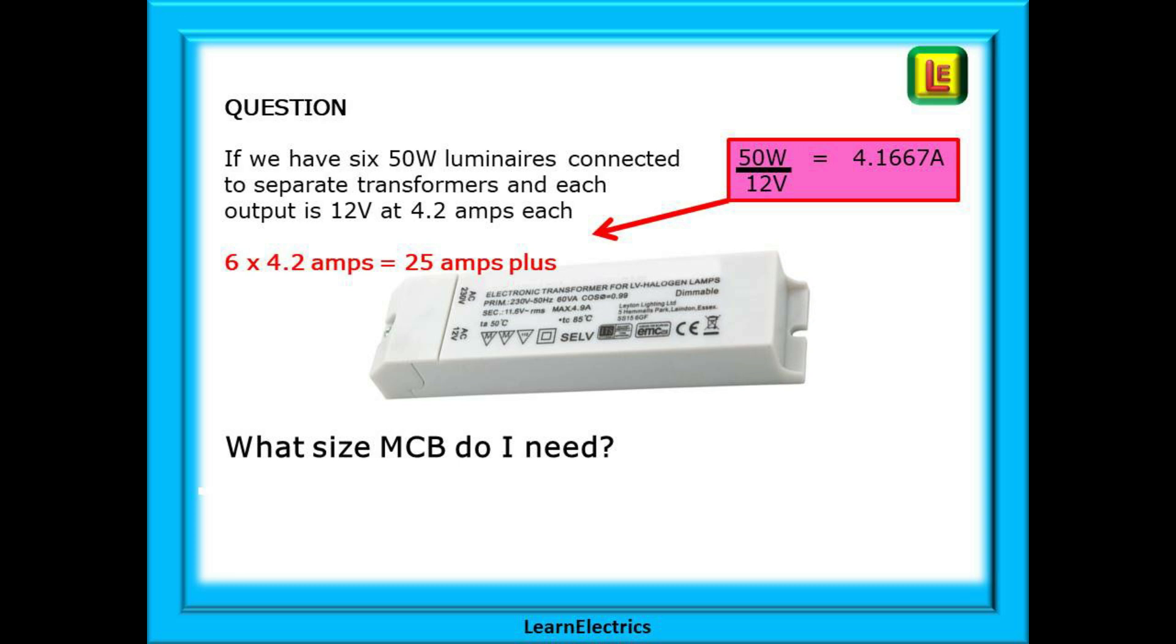We have six 50-watt luminaires connected to six separate transformers, and each transformer output is 12 volts at 4.2 amps each. If we add up all the loads for the lights, we get 6 times 4.2 amps, which is over 25 amps.